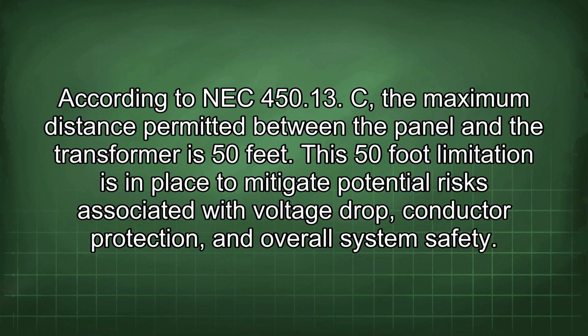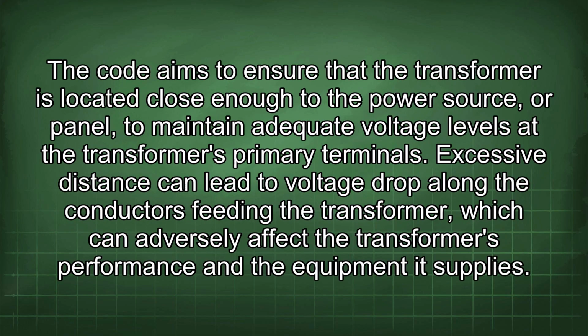This 50-foot limitation is in place to mitigate potential risks associated with voltage drop, conductor protection, and overall system safety. The code aims to ensure that the transformer is located close enough to the power source or panel to maintain adequate voltage levels at the transformer's primary terminals. Excessive distance can lead to voltage drop along the conductors feeding the transformer, which can adversely affect the transformer's performance and the equipment it supplies.